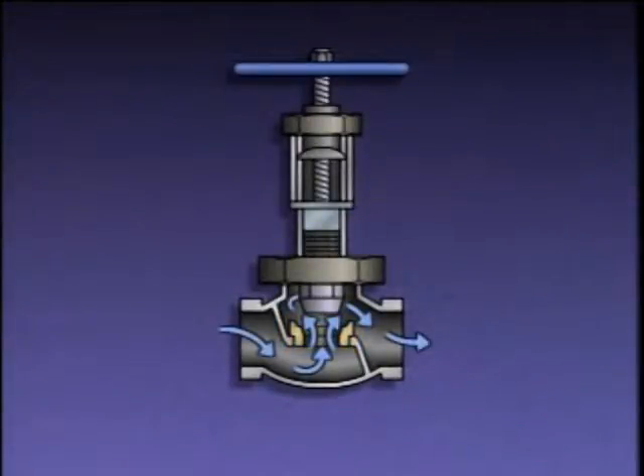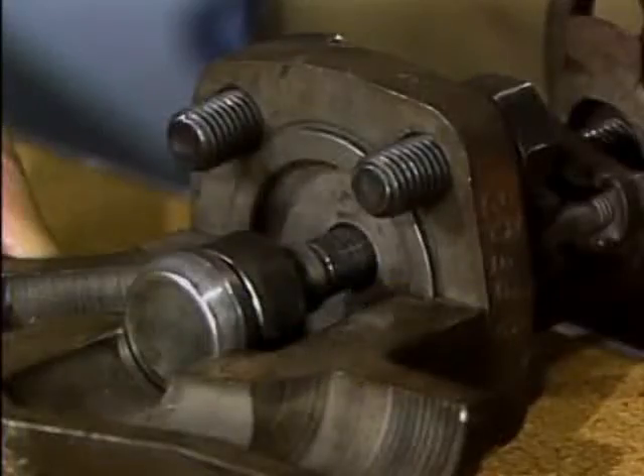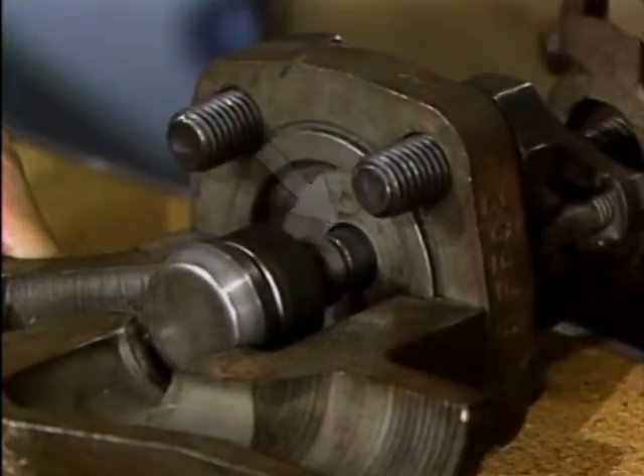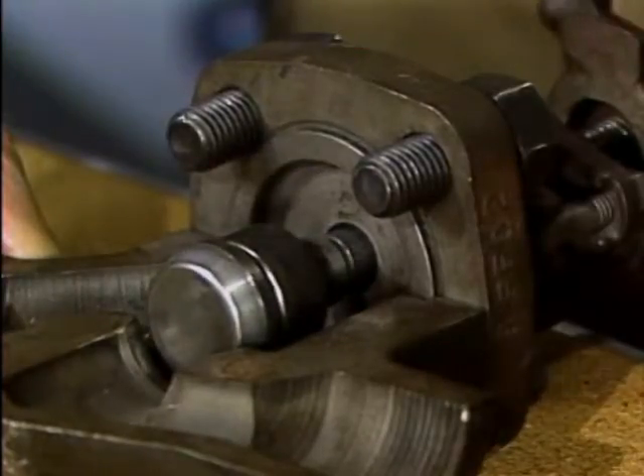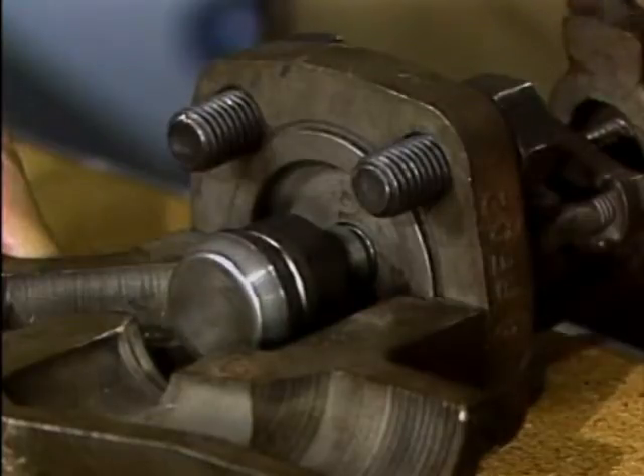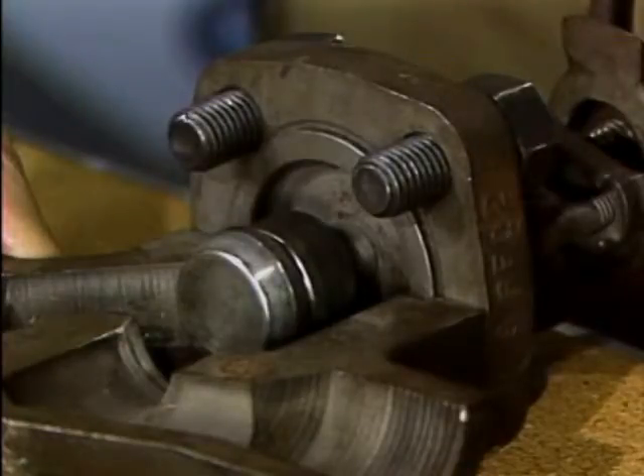This design feature prevents uneven wear of the seat and disc. In addition, some globe valves have a back seat. When the valve is fully open, the top side of the disc seats against the back seat. This prevents the packing from being constantly exposed to piping system pressure and reduces the likelihood of a packing leak.